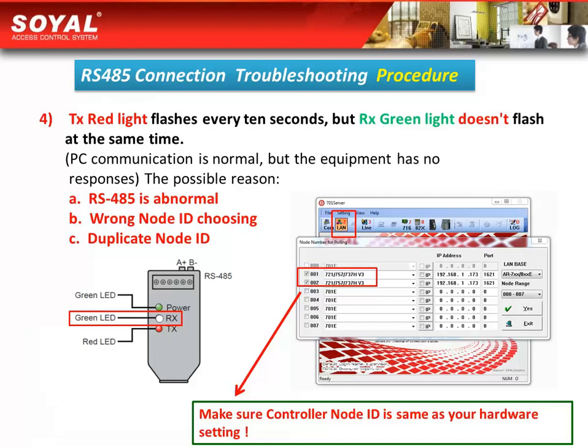Fourth, check the TX red light to see whether it flashes every 10 seconds. If we confirm that the TX red light flashes every 10 seconds but the RX green light does not flash at the same time, it means the PC communication is normal but the equipment has no response. There are three possible reasons: first, the RS485 is abnormal; second, the wrong node ID was chosen; and third, duplicate node ID.